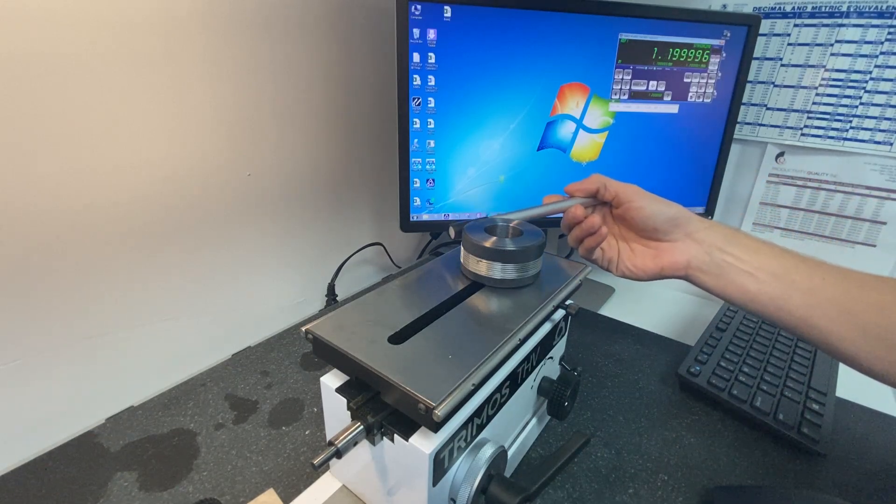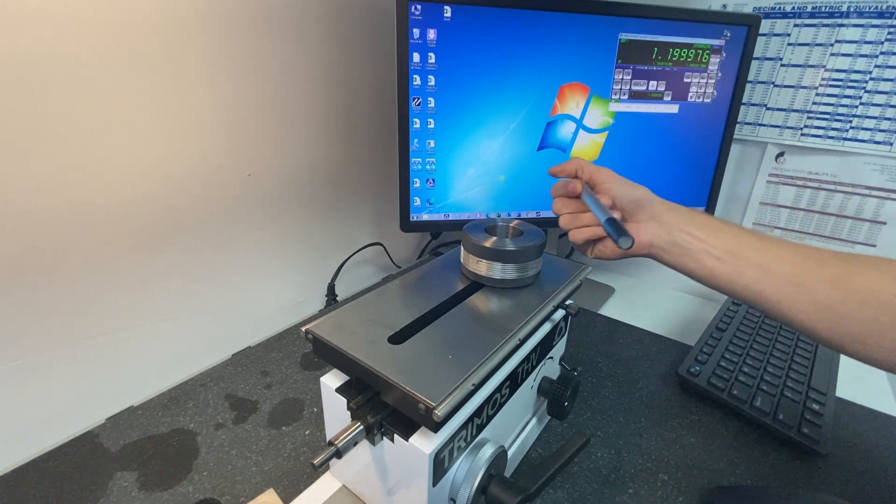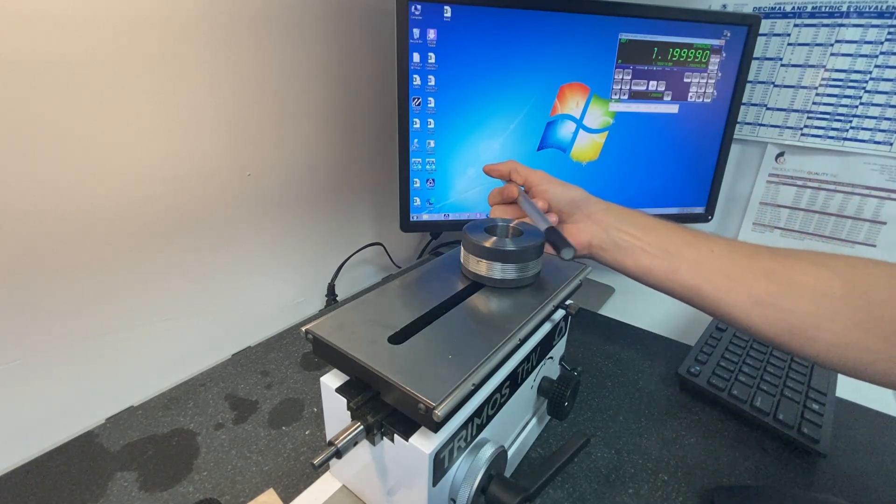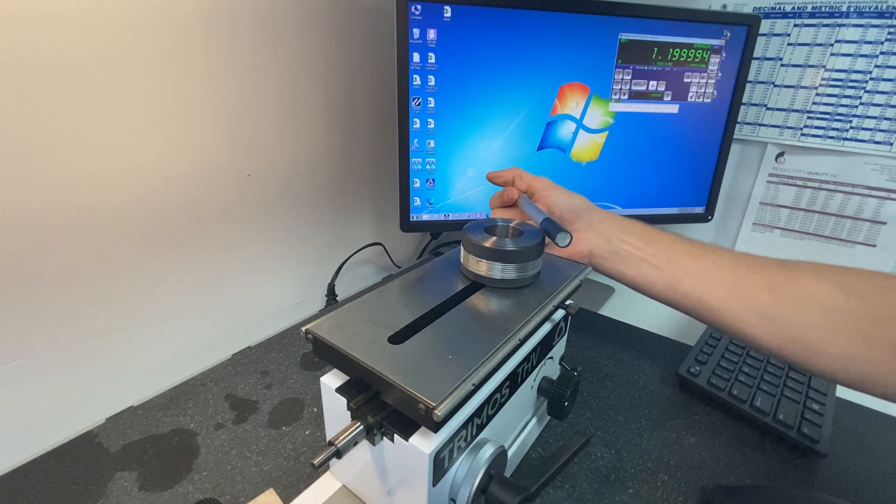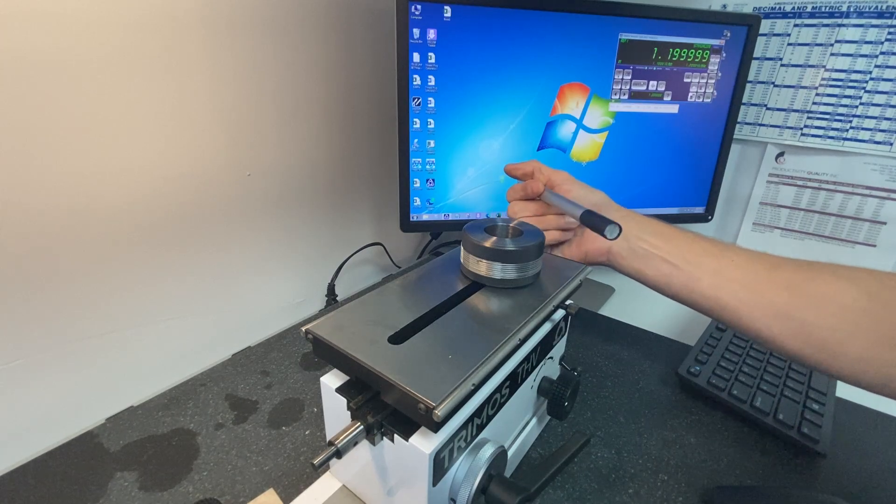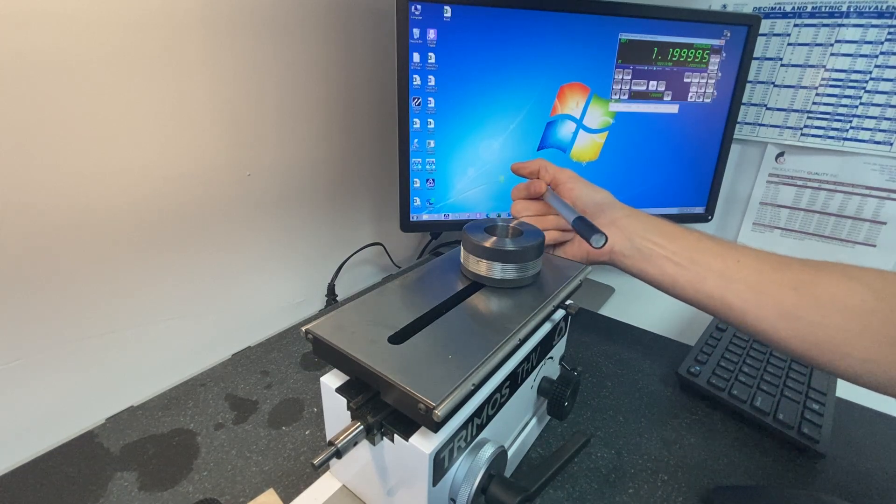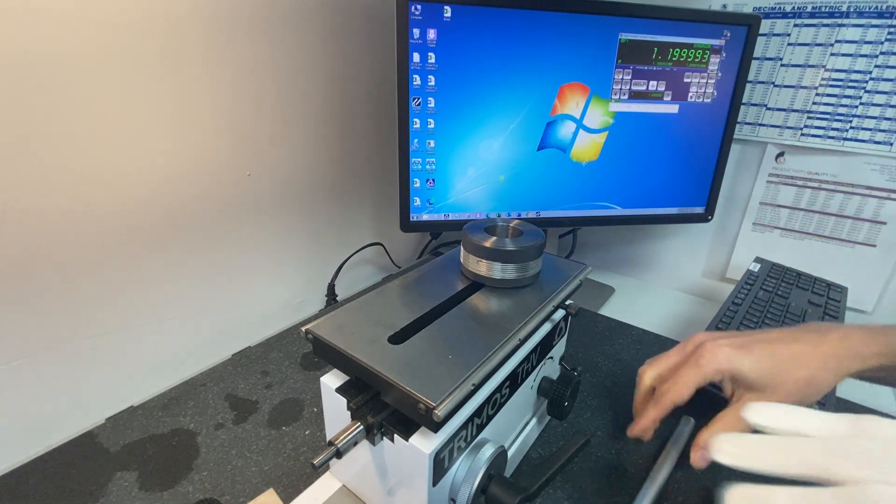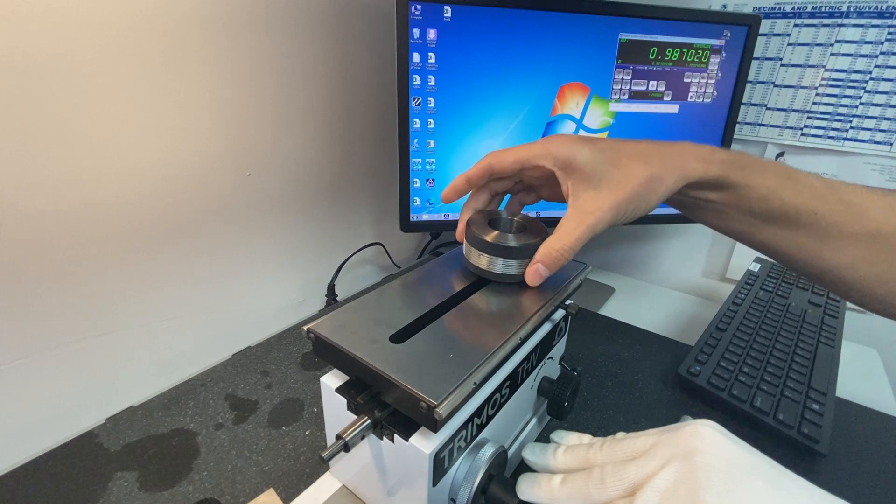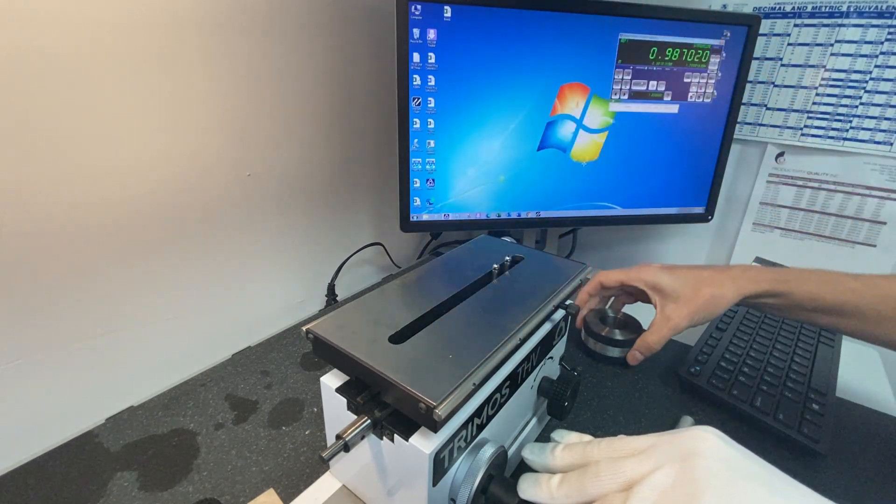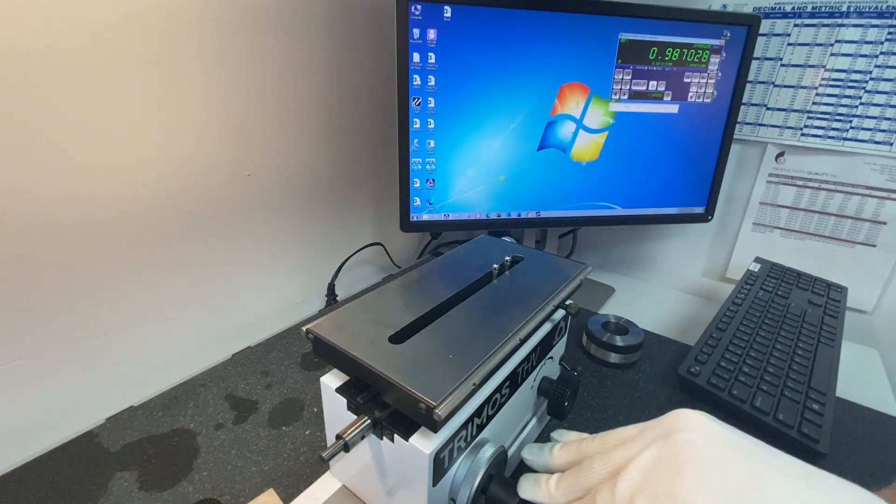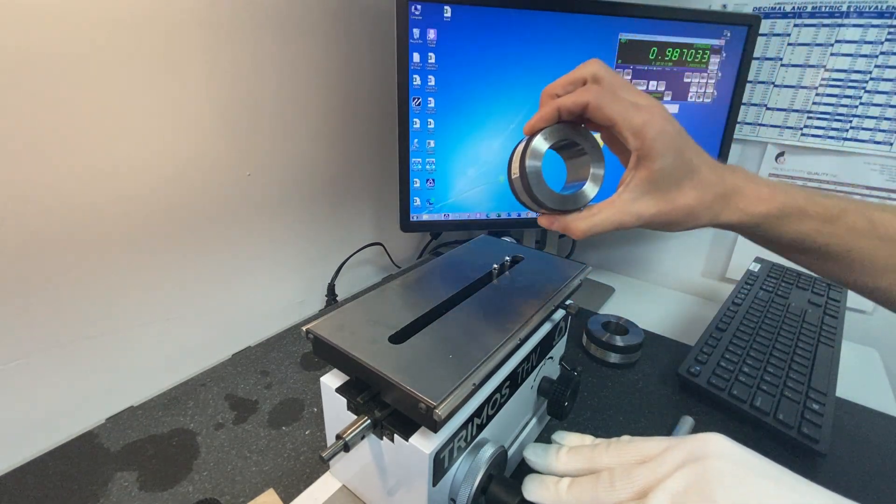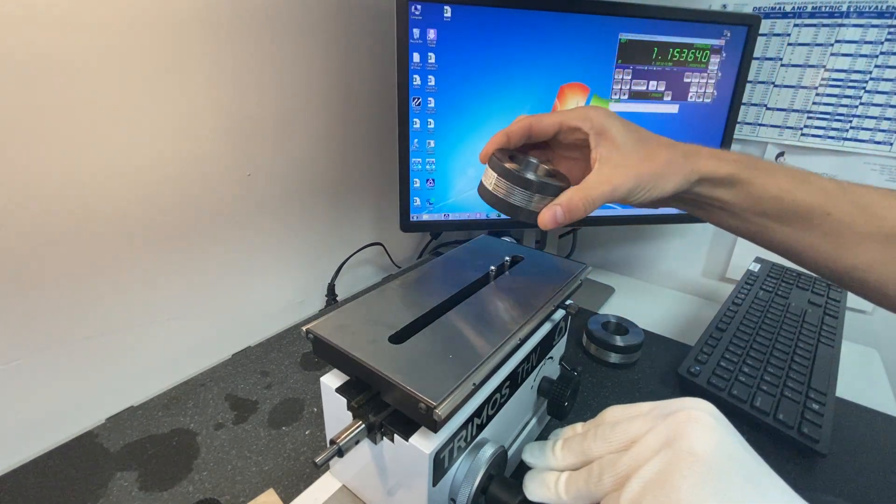So we're setting our reference ring, the QTC ring, and then next we will measure, that looks to be about right, the unit under test ring, which is this one.